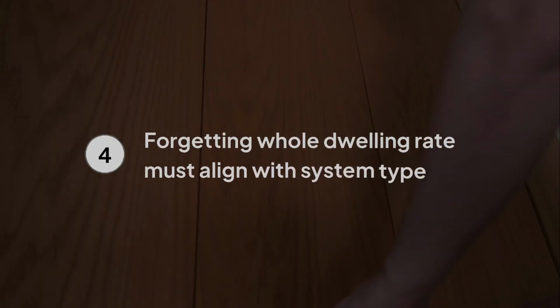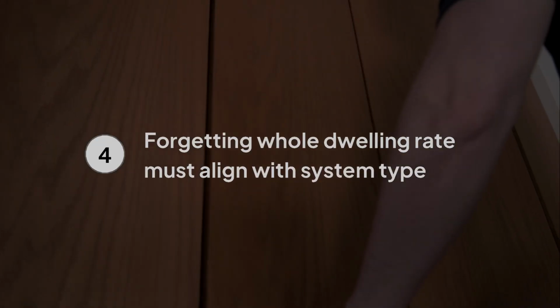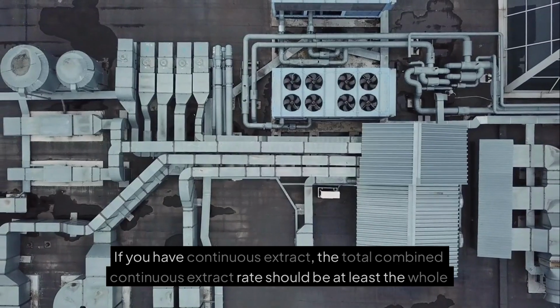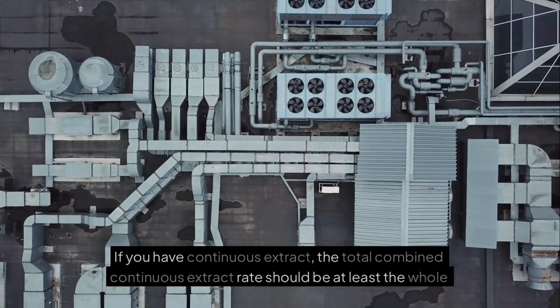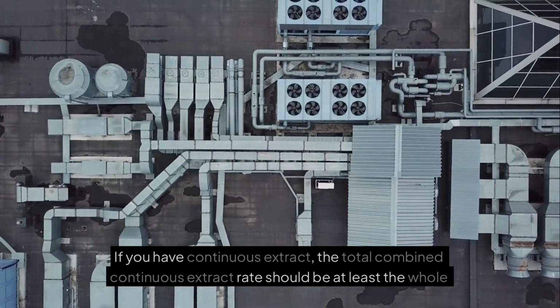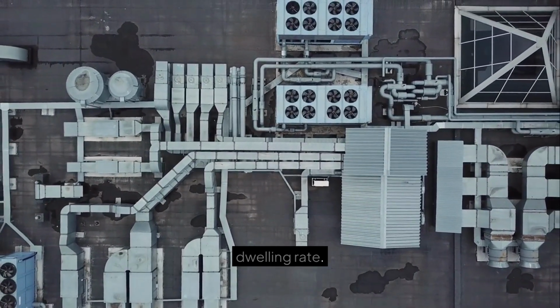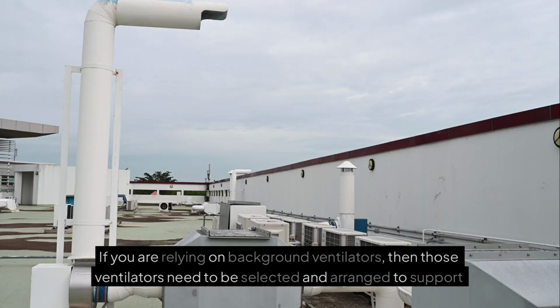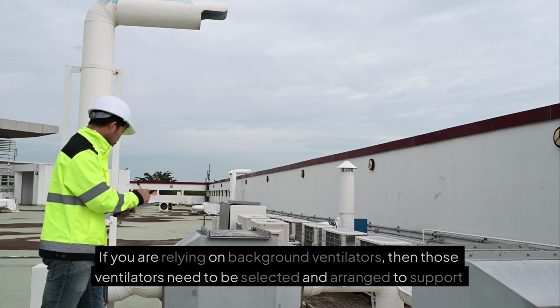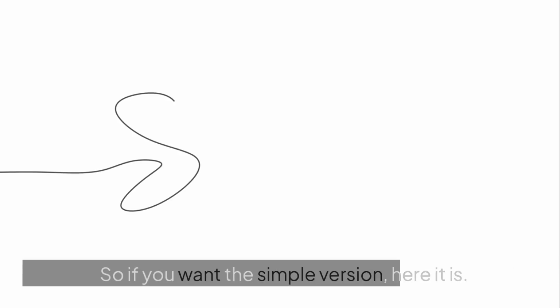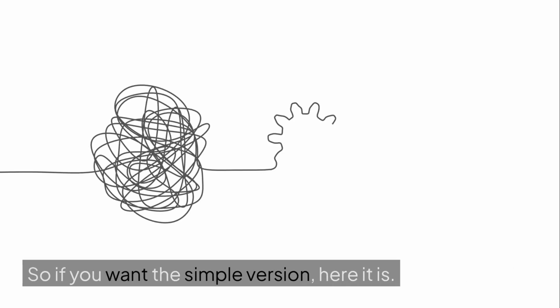The fourth is forgetting that the whole dwelling rate needs to tie back to the system type. If you have continuous extract, the total combined continuous extract rate should be at least the whole dwelling rate. If you are relying on background ventilators, then those ventilators need to be selected and arranged to support the strategy properly. So if you want the simple version, here it is.